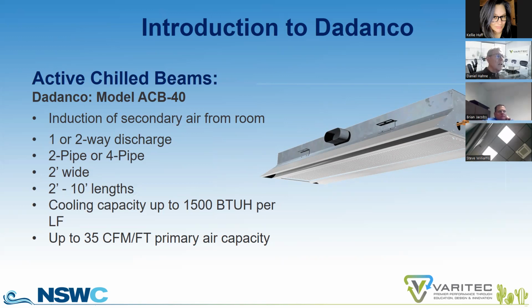So we have a dedicated hot water loop serving each chill beam versus the chill water loop. And that gives a little tighter control for heating, but it adds copper and it adds first cost. So something to consider. Chill beams can come in 2-foot lengths all the way up to 10-foot lengths.